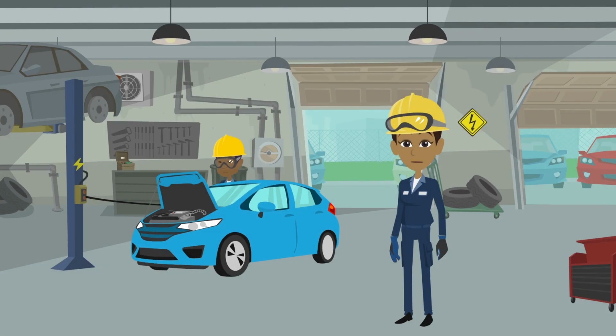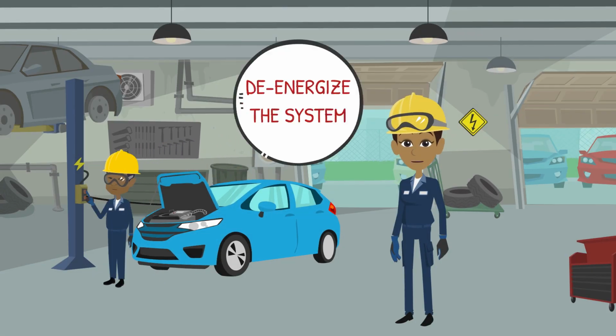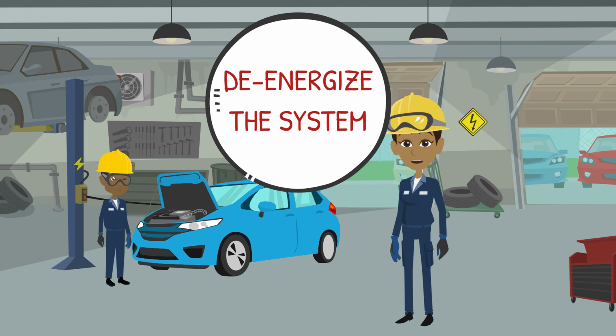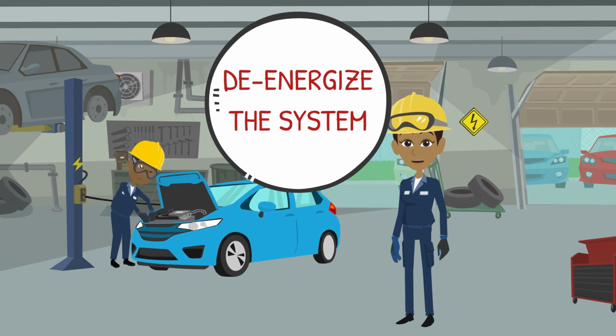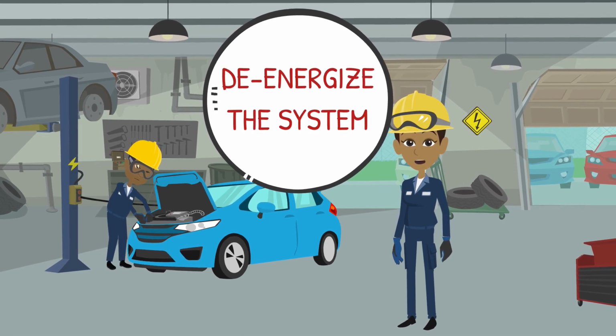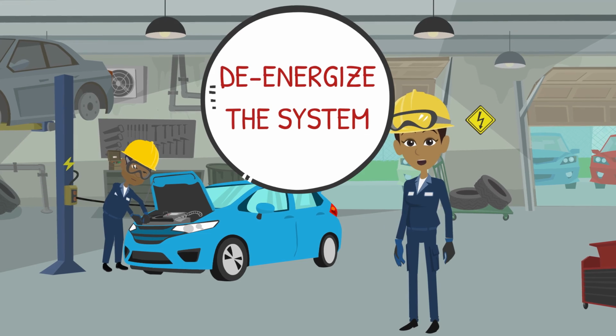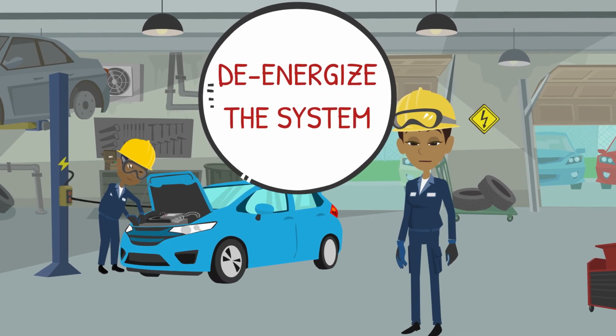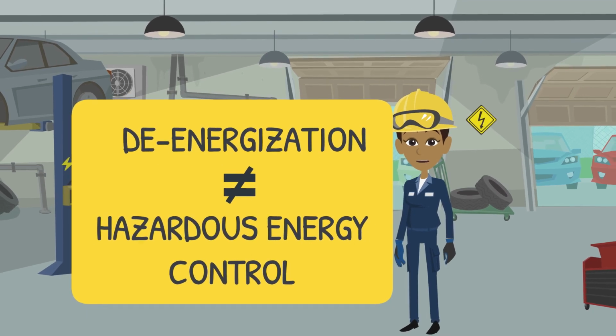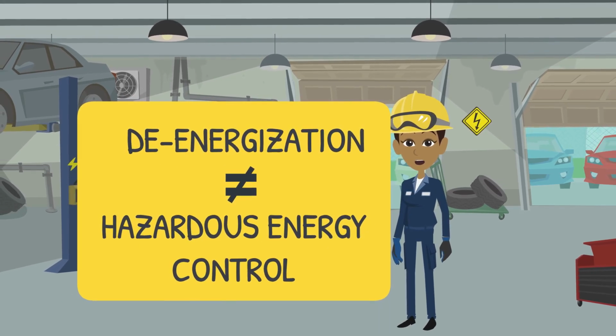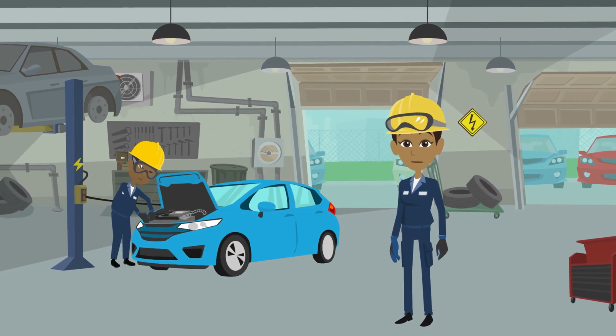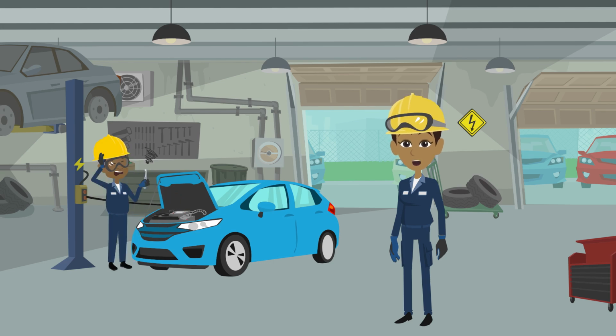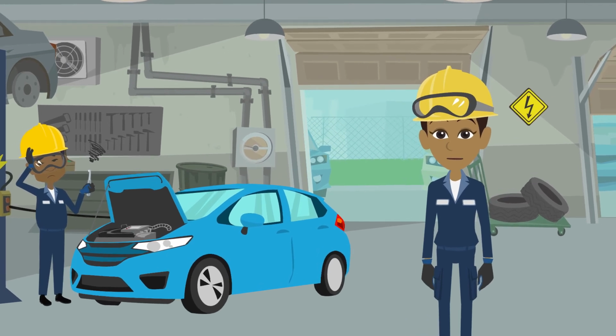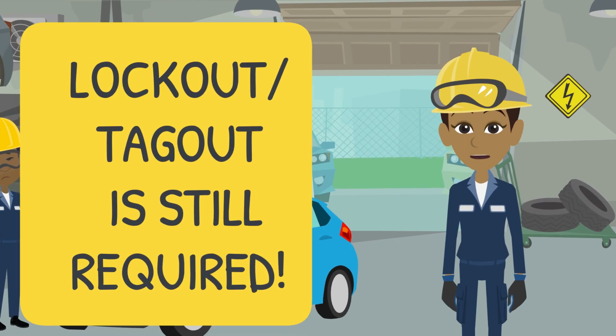It is critical for anyone working in or around EV batteries to de-energize the system before doing any work. This will vary from vehicle to vehicle, so review the manufacturer requirements for de-energization and lockout-tagout. Remember that de-energization and hazardous energy control are not the same. Pulling a high-voltage plug or fuse out is not adequate for hazardous energy control—lockout-tagout is still required.